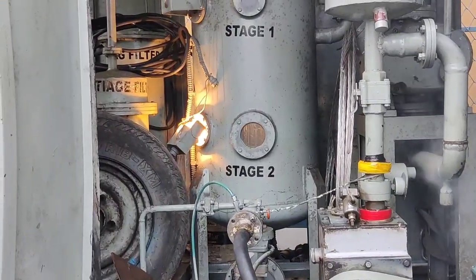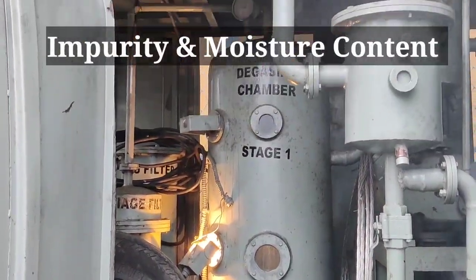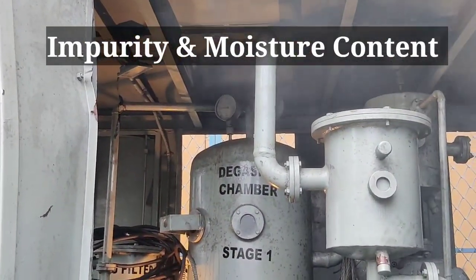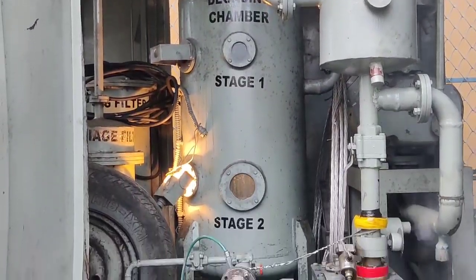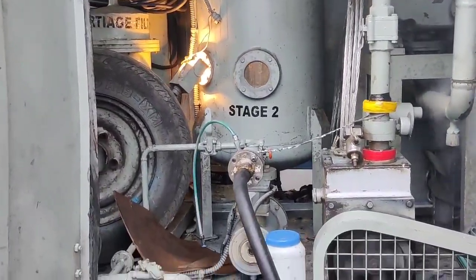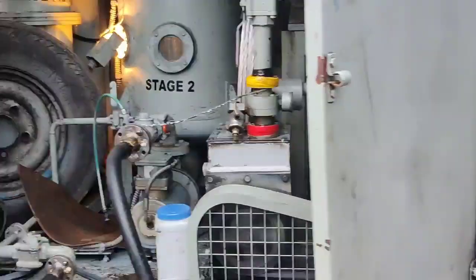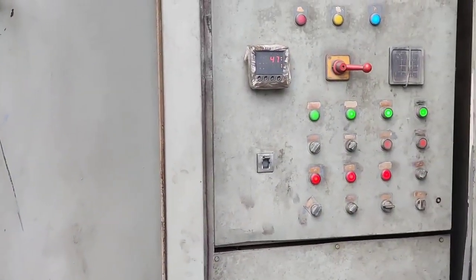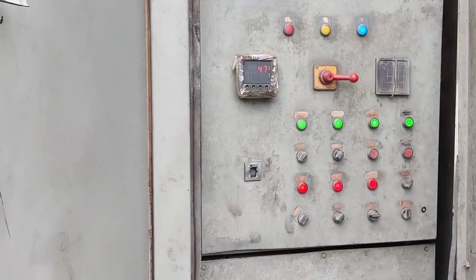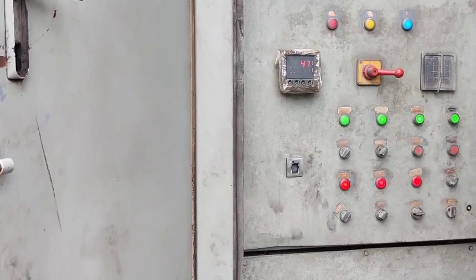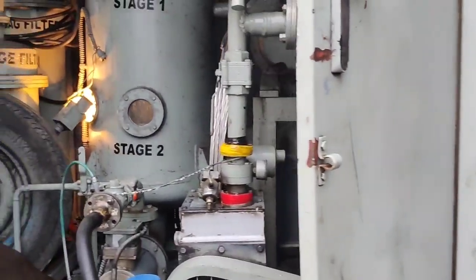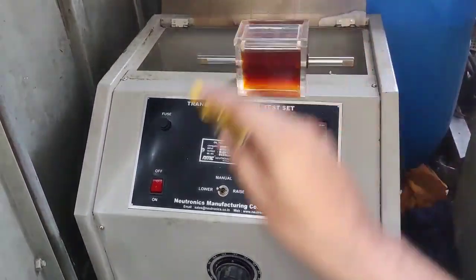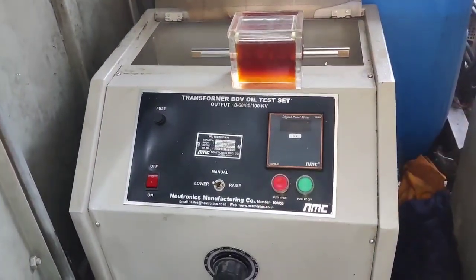You can see here, if transformer oil has moisture content and impurities, then the transformer oil BDV value will decrease. So to use transformer oil, we need to filter it. You can see here, after filtration, the transformer BDV value shows 47. So let's start the video and first identify how to check transformer oil BDV value.